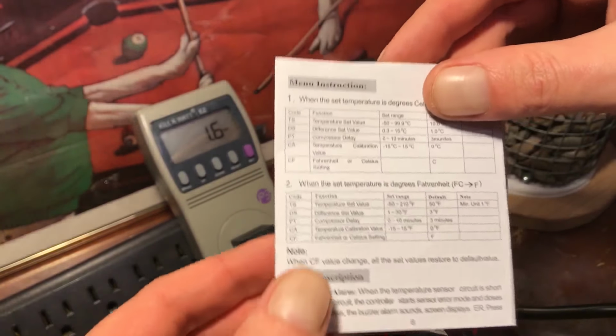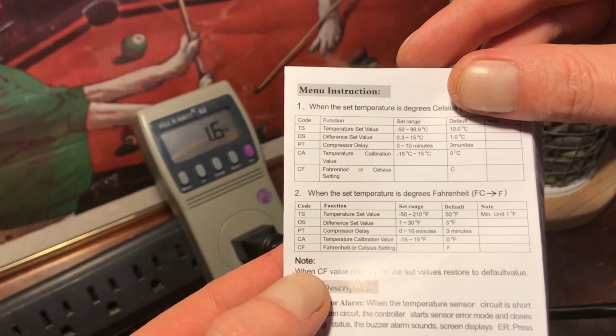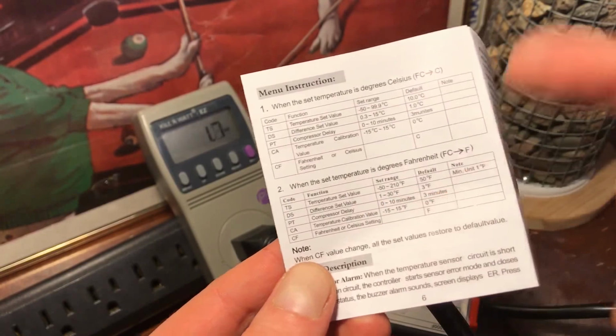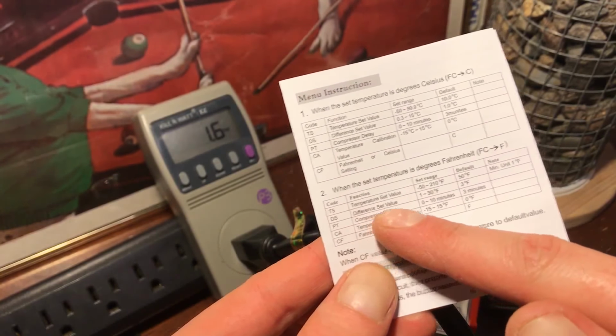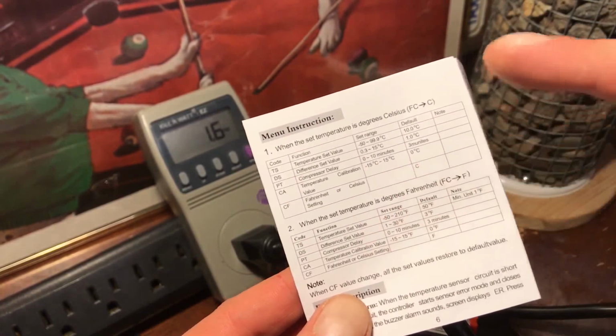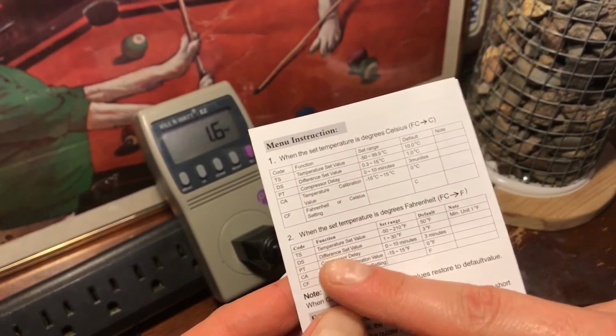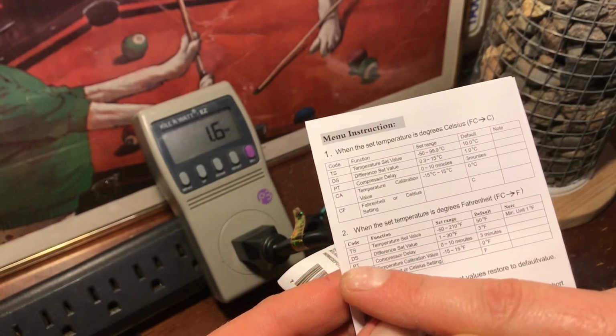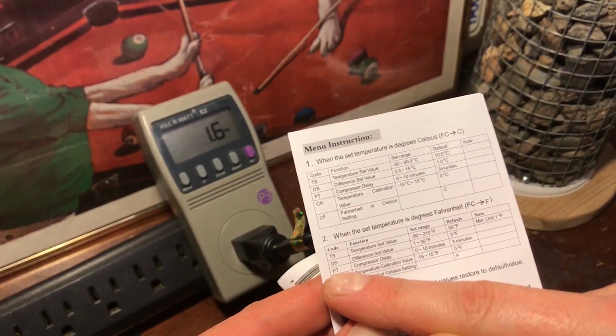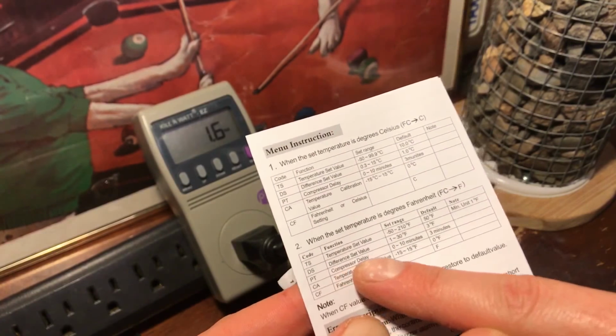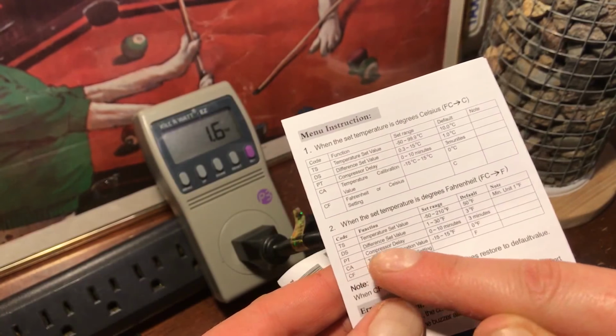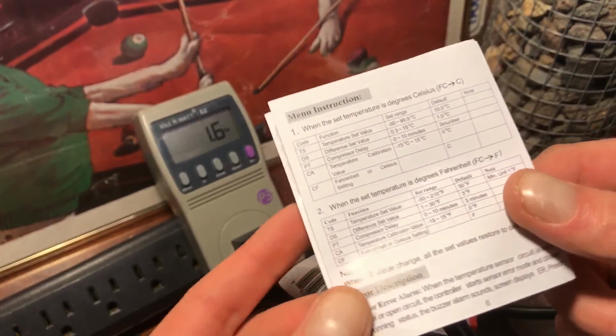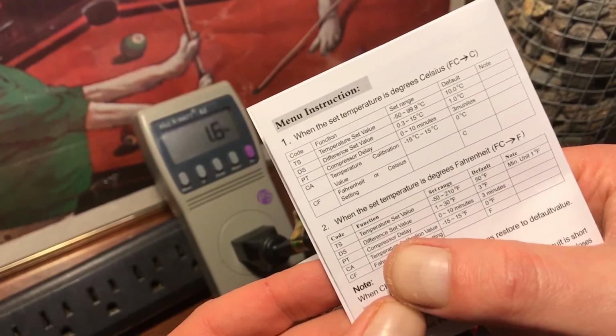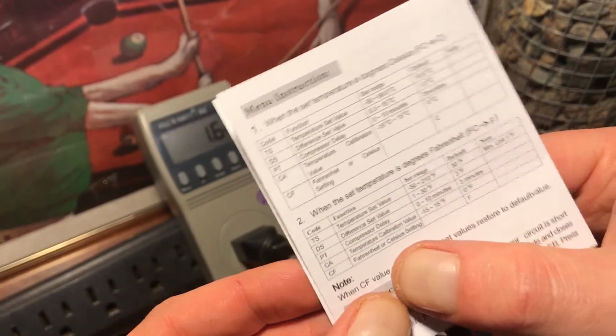I got my instructions here that tell me what the different codes are in the settings. You can see TS is temperature set value, that's the set point. DS is differential set value, so that's going to go up and down from the set point, however many degrees you enter into the DS value, and then turn on the heater or the cooler, respectively. PT is compressor delay, so in time. So I guess if you have a compressor, it'll delay before it kicks in, so it's not constantly cycling it on and off, I guess. And then CA is a calibration value, so if the thermocouple is off, we can calibrate it with that. And the CF switches between Celsius and Fahrenheit.